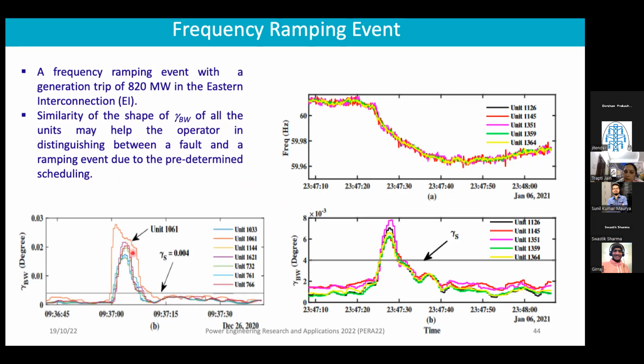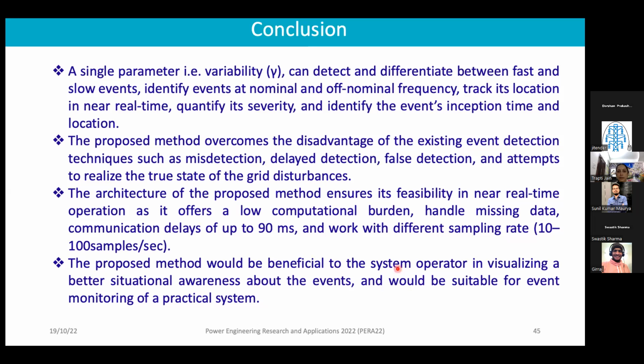Here, when the event happened, the shape was different for all these units, but here it is the same. So now we can conclude this presentation. We were able to define a single parameter, variability, which was able to detect and differentiate between fast and slow events and identify events at nominal and off-nominal frequency at its location in near real time, and quantify its severity as well as identify the event's inception time and location. The proposed method also overcomes the disadvantages of the existing event detection techniques, such as misdetection, delayed detection and false detection. The architecture of the proposed method ensures its feasibility in near real-time operation as it offers a low computational burden, handles missing data and communication delays of up to 90 milliseconds, and is able to work with different sampling rates also.